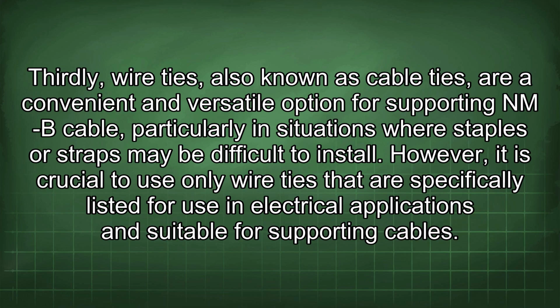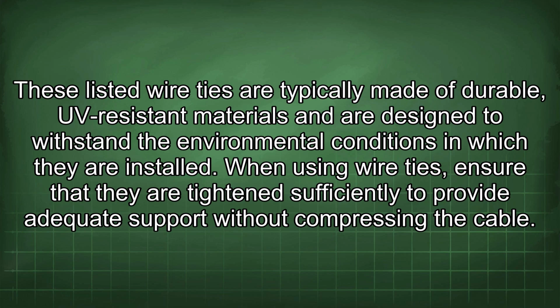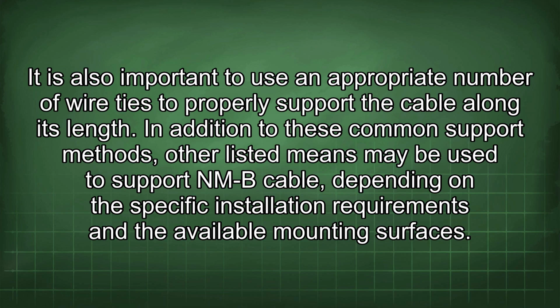Thirdly, wire ties, also known as cable ties, are a convenient and versatile option for supporting NMB cable, particularly in situations where staples or straps may be difficult to install. However, it is crucial to use only wire ties that are specifically listed for use in electrical applications and suitable for supporting cables. These listed wire ties are typically made of durable, UV-resistant materials and are designed to withstand the environmental conditions in which they are installed. When using wire ties, ensure that they are tightened sufficiently to provide adequate support without compressing the cable. It is also important to use an appropriate number of wire ties to properly support the cable along its length.